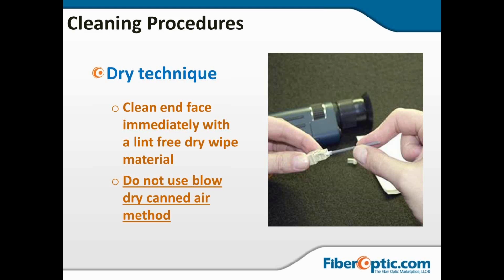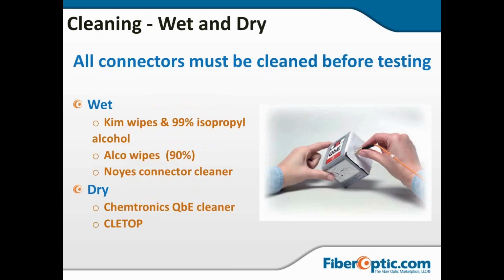Anyway. The reason you don't use canned air is that the canned air is pushed by a propellant. It's not just pressurized air. There's a propellant, and that propellant will leave a residue. So the canned air method is pretty much pointless. You're going to have to clean after it anyway. So again, all connectors should be cleaned before testing.